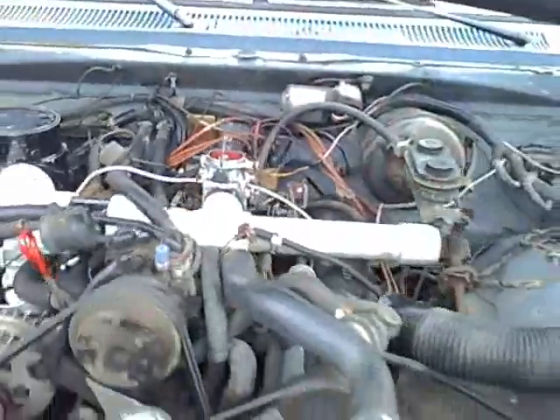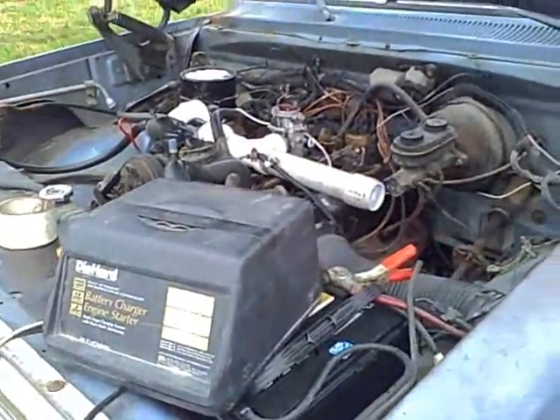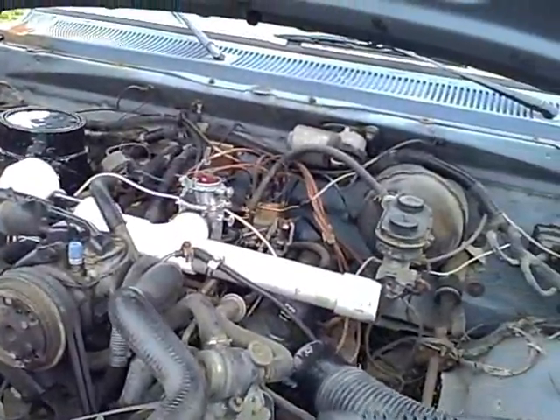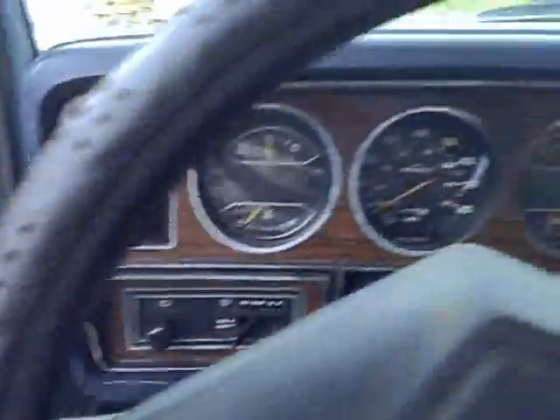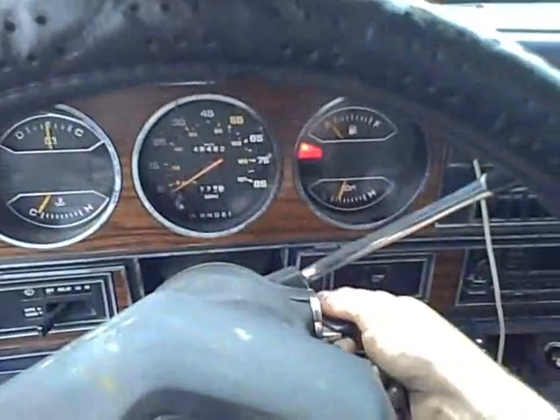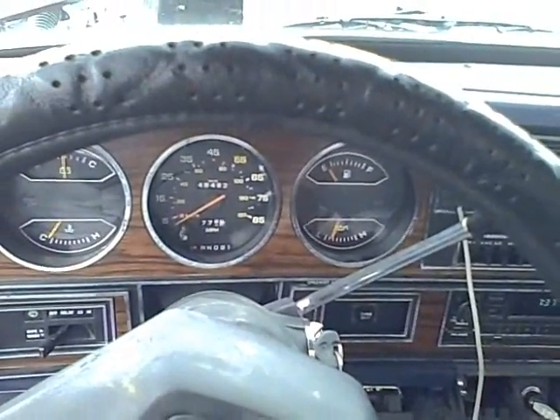I'm getting this behavior really consistently. I can shut the valve, shut off the fan, and start it up, and it'll start and then die — and I can do it over and over again. It's good gas, but you can see what we've got here. I'll shut the valve... and it dies.